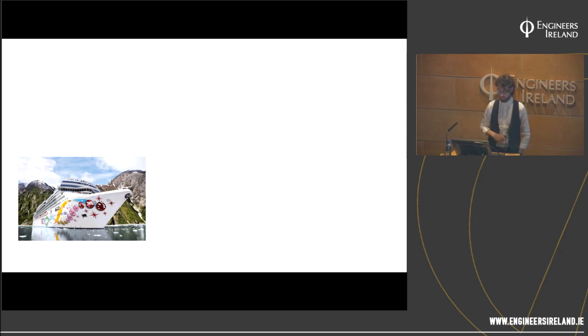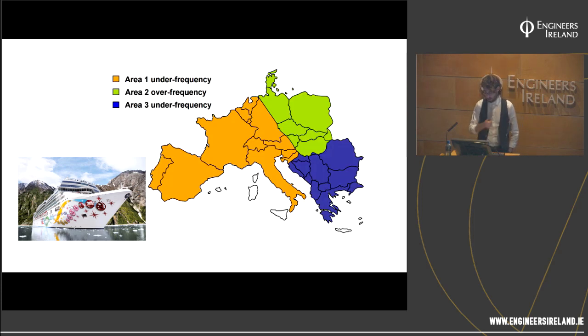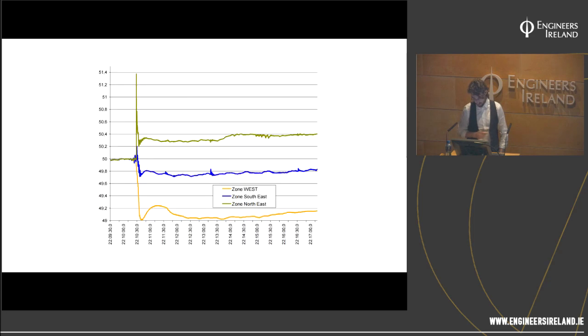And once they disconnected this line, surrounding lines got overloaded, and you had a cascade tripping of transmission lines throughout Europe. And what happened was that the European grid split into three regions, and there's the accompanying frequency response. I suppose the point of this graph is to show it ain't just small systems like Ireland for which inertia matters. Okay, so I suppose going forward, actually, Ireland is small, so I'm not sure it'll matter. Maybe if you want to prevent system splitting between Northern Ireland and Ireland, but the location of the inertia might matter in the future as well.